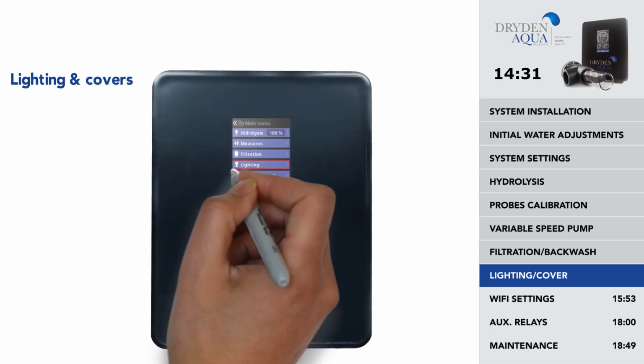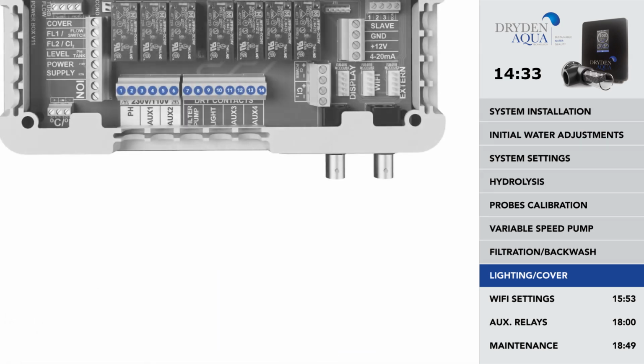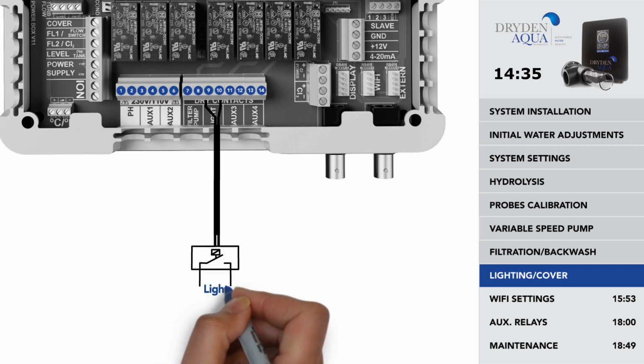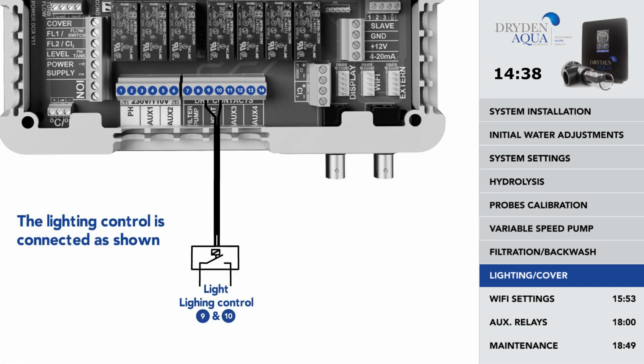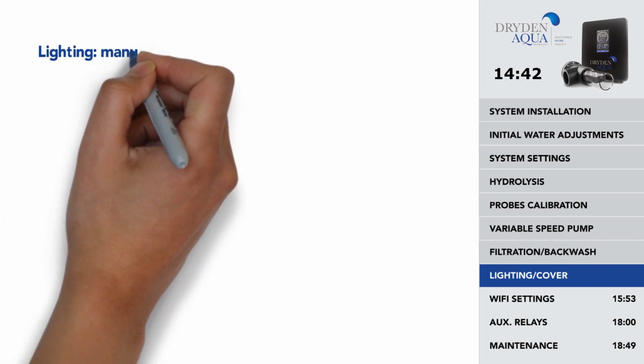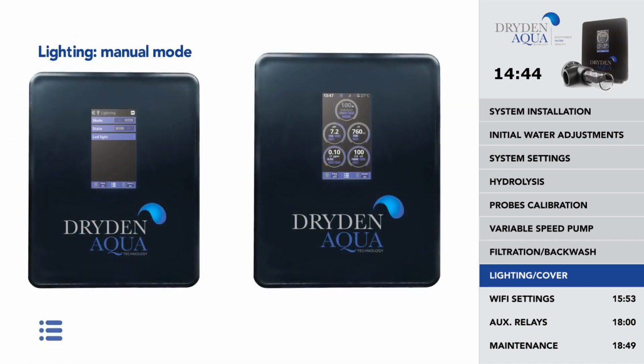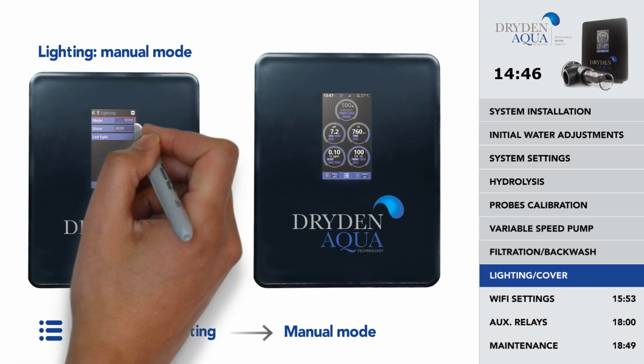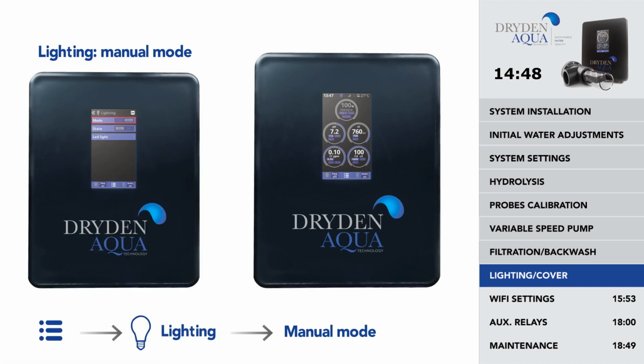Lighting and covers. The DA Gen also offers the possibility to connect and control lights. Connect the lighting control as shown. To control the lights manually, go to the menu Lighting in the main menu and select Manual Mode. You can also activate the lights manually by pressing the shortcut on the bottom right side of the main display.